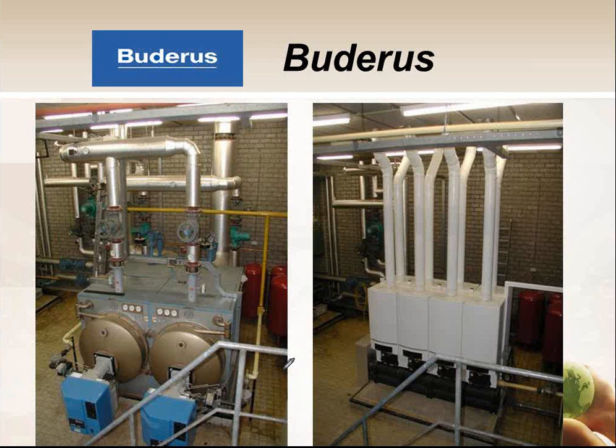All the boilers we're talking about so far have been water tube boilers. So water's in the tube, flames going around the tube. But take that burner out and clean in between all of those tubes to get any debris out of there, right? Vacuum it out, clean it up. On the water side, pretty much the only thing we do, Dan, is that on all the boilers we do anyway at TEC, we put a strainer on the return water side. So that strainer can catch all the debris that might be in the water, whatever it is. If we got a little flux in the pipe from when we connected it up originally or whatever it is, let that strainer collect all that crap, and then we'll blow the strainer out, right?